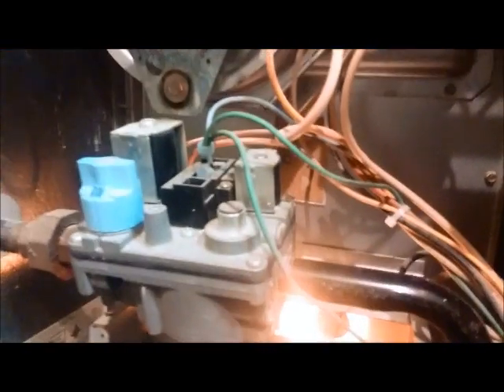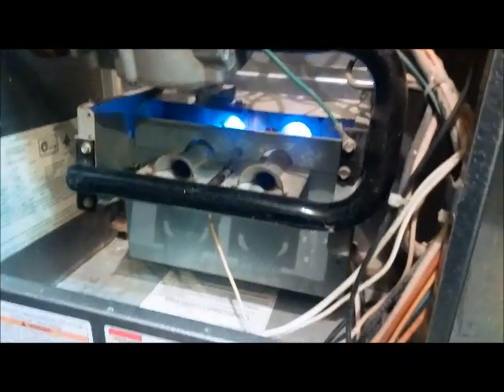Our inducer came on. Igniter glowing. You're going to hear the gas valve click — there it clicked. You should have flame. There it goes.